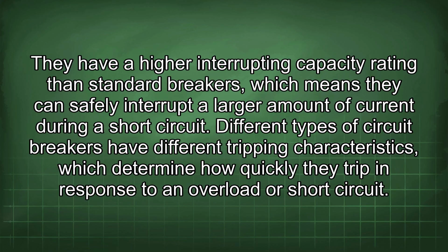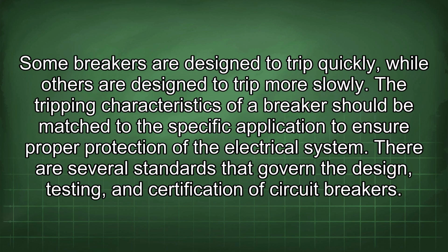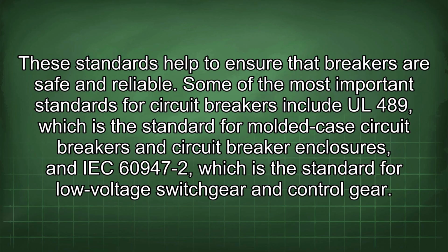Different types of circuit breakers have different tripping characteristics, which determine how quickly they trip in response to an overload or short circuit. Some breakers are designed to trip quickly, while others are designed to trip more slowly. The tripping characteristics of a breaker should be matched to the specific application to ensure proper protection of the electrical system. There are several standards that govern the design, testing, and certification of circuit breakers. These standards help to ensure that breakers are safe and reliable.